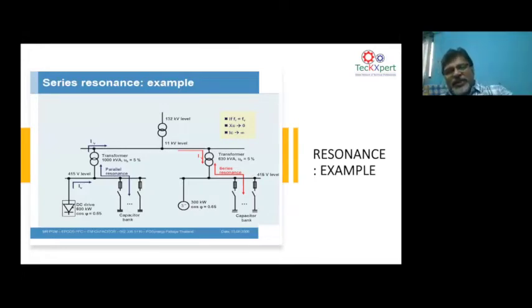That is how you can see the rest of the network can send a lot of current. The red line shows the current flowing in at the time of series resonance. That means all your capacitors will get damaged, your transformer will get heated, and your cables will get heated. That means even a series resonance is dangerous if you have harmonics producing load.